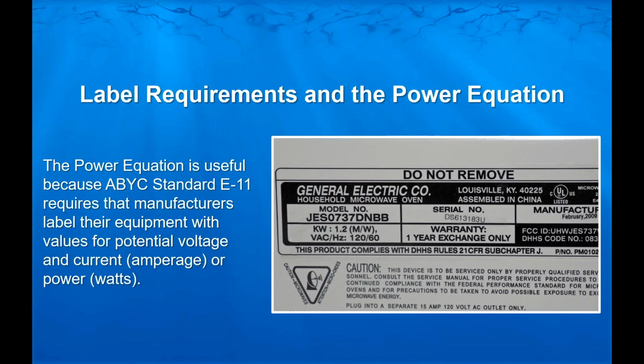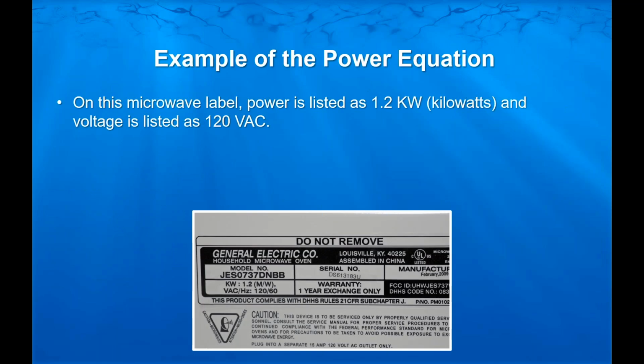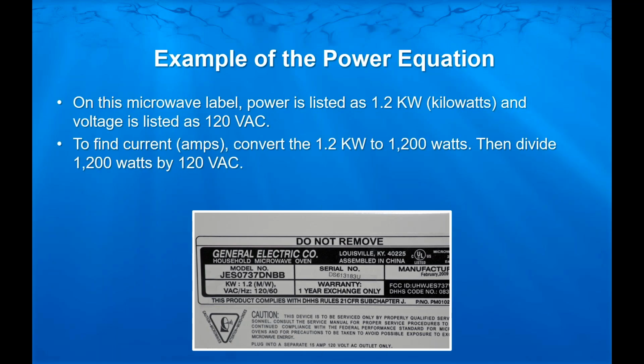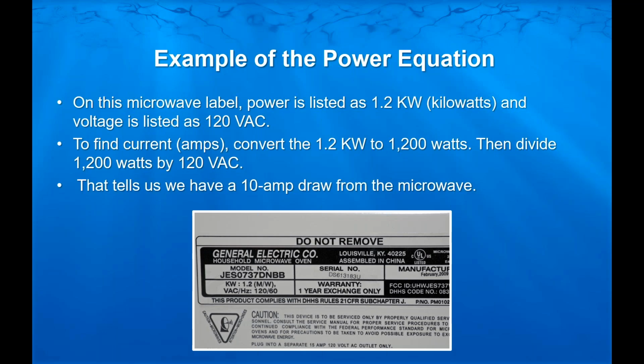This equation is very useful because the ABYC standard E11 requires all manufacturers to label their equipment with values for potential voltage and current or power. On this microwave label, power is listed at 1.2 kilowatts and the voltage is 120 volts. To find the current, we're looking for the amperage. We're going to convert that 1.2 kilowatts to 1200 watts. One kilowatt is 1000 watts. Then divide the 1200 watts by 120 volts, and that tells us we have a 10 amp draw from the microwave. It's very easy to do, and that's practical application when you need to figure out overcurrent protection or wire sizing for an appliance, for any component. If you're not given what the amperage draw is, that's how you can figure out what you need to deal with.